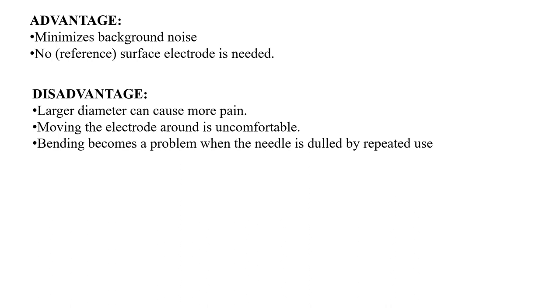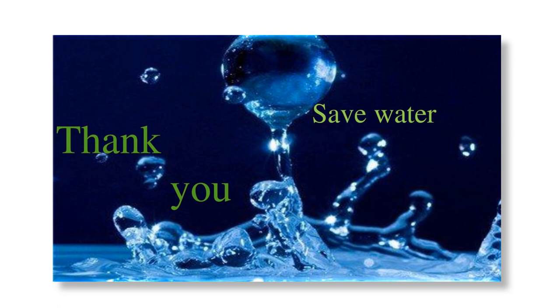The major disadvantage of the coaxial needle electrode is that the larger diameter can cause more pain to the patient, and moving the electrode around also makes it uncomfortable. Bending becomes a problem when the needle is dulled by repeated use, but this needle can be resharpened with a fine hollowed stone. This is all about needle electrodes and depth electrodes. Hope you all enjoyed this session — thank you.